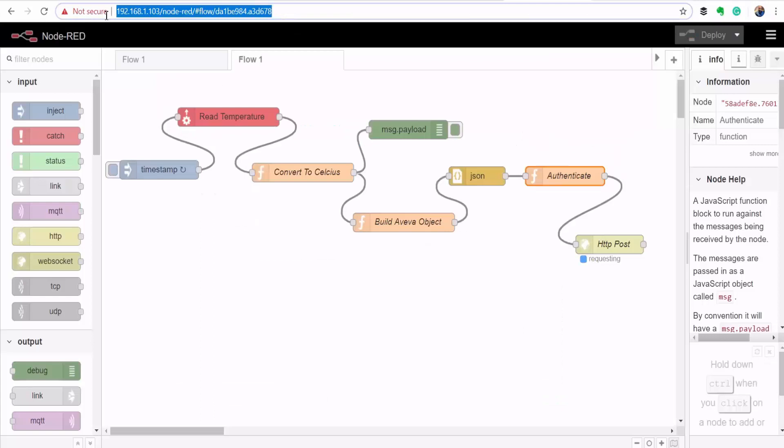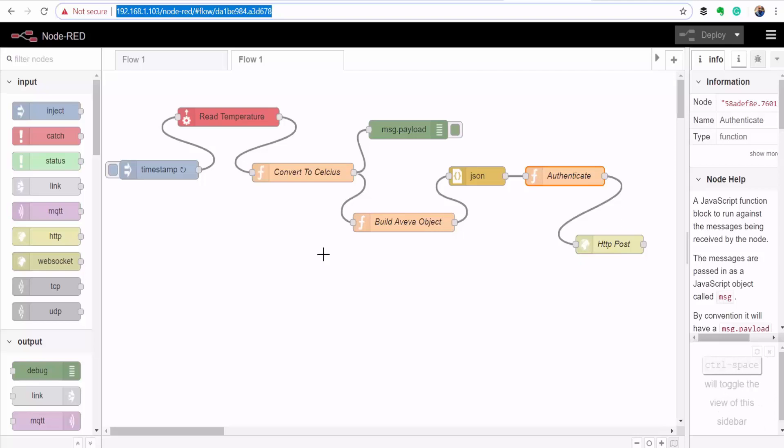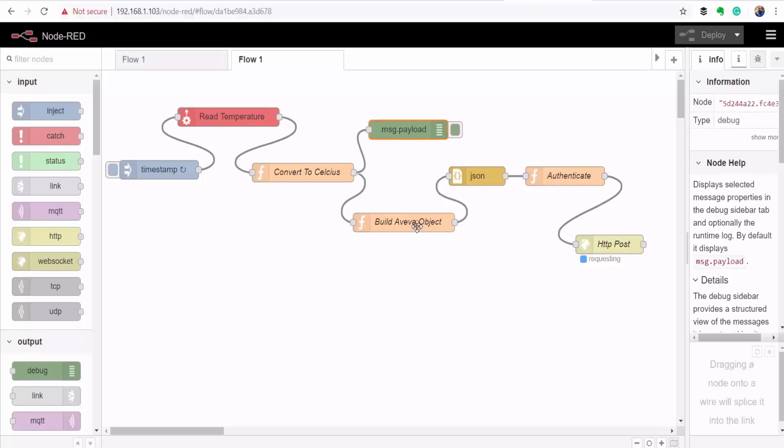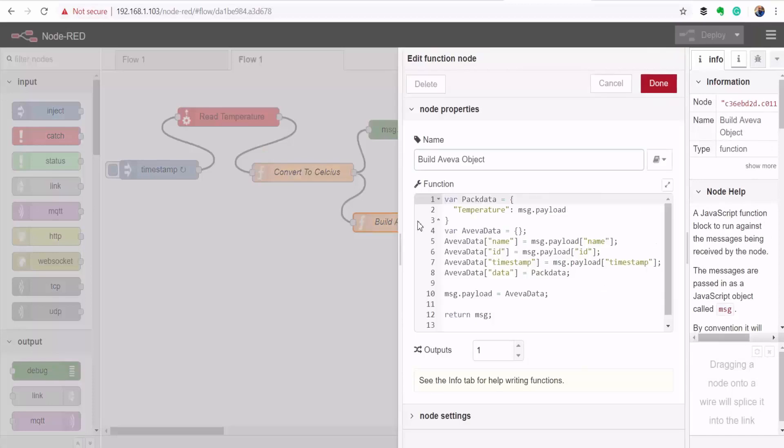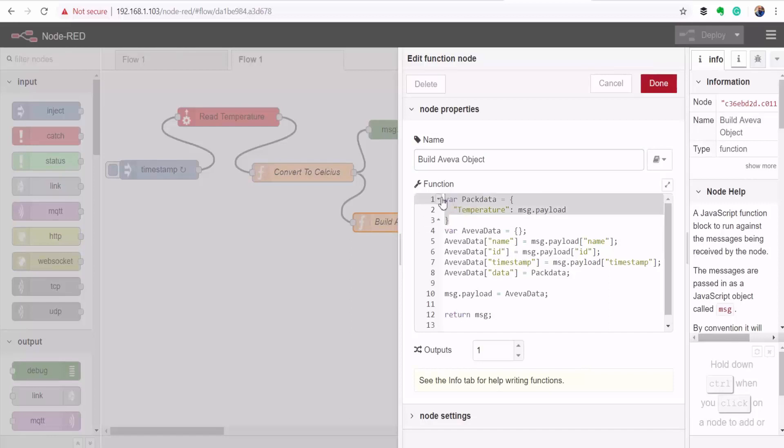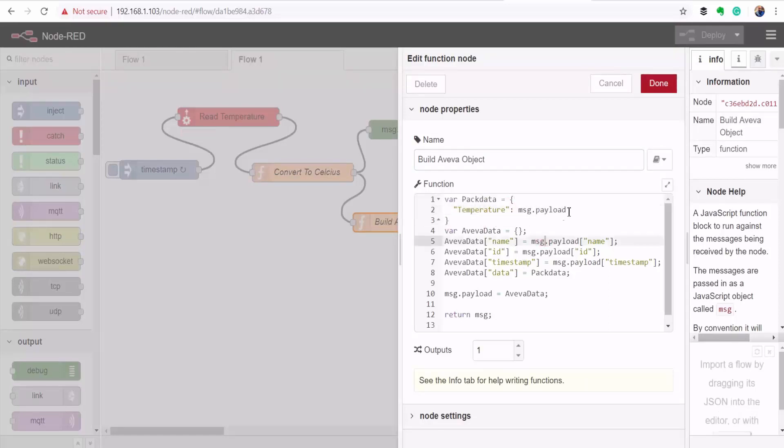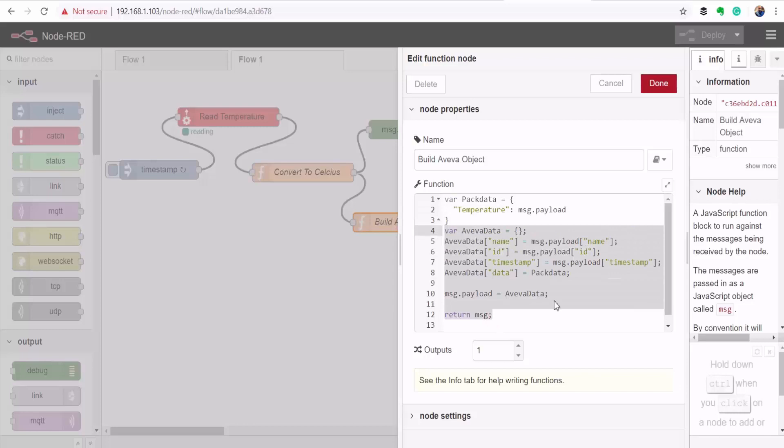So right now I'm on the Node-RED platform running on my Groov EPIC controller. I've put together this flow. Here I'm using the Groov EPIC controllers Node-RED package to read the temperature value after every three seconds. And then here I'm using a function block to build my AVEVA Insight message. So this is a JSON object, and then I'm calling that object temperature and then assigning it the value of my temperature sensor. And then I'm bundling all of that with the ID and the timestamp for AVEVA Insight platform.